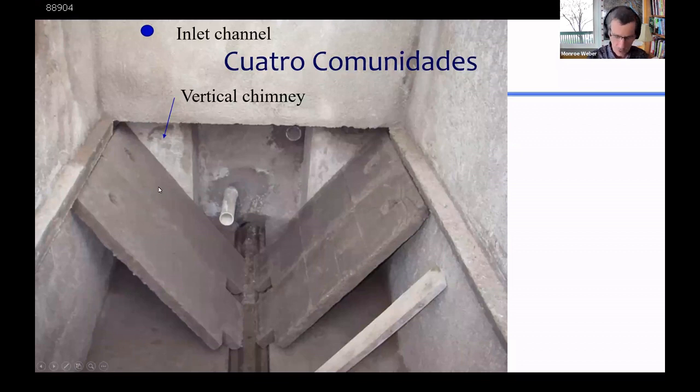and then it will pop out underneath this sloped bottom. So this is where the water travels. It goes down, and then it goes down the chimney, then it pops out of a hole underneath those slope pieces. It comes up through the port that was at the very bottom of the sedimentation tank that these slope pieces create. And it looked just like, this is a wonderful design. But maybe you're already thinking you see some problems with this based on what we've been learning.